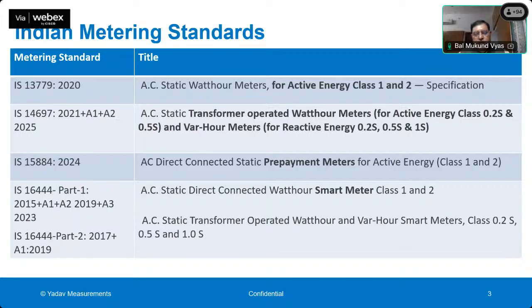So if it is a simple meter, most of the meters which we use in our houses are class 1 meters, which are BIS marked as per IS 13779, which is for AC static watt hour meters, active energy meters. If it is a CT operated meter, then it has to be tested as per IS 14697. Then there are standards for prepayment meters.